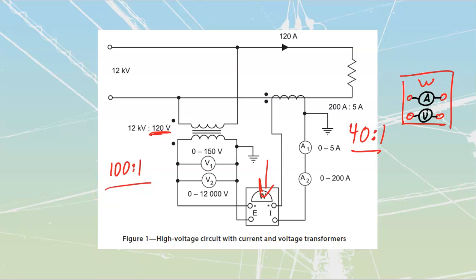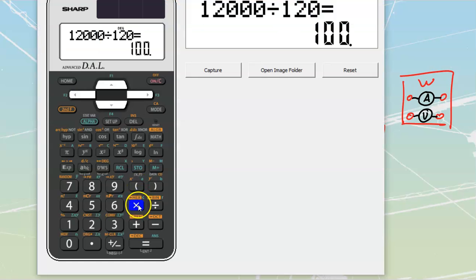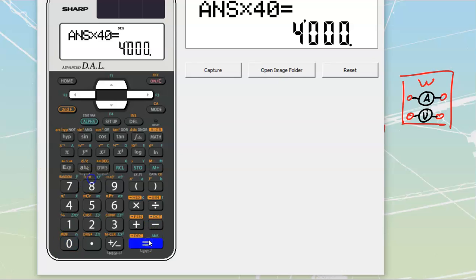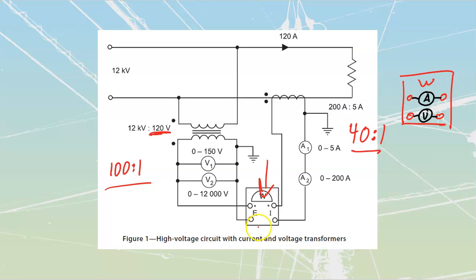That watt meter multiplier is going to be this times this. In other words, if I take 40 times 100, we can do it mentally as well, but let's just do it in the calculator. 100 times 40 gets me to 4,000. In other words, my watt meter multiplier is going to be 4,000 to 1.